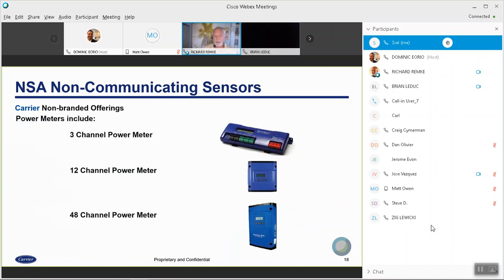And we also have these BACnet power meters for sub-metering. We have a 3-channel model, a 12-channel model, and a 48-channel model. And all of those are in our catalog. And there's a whole series of CTs and VTs that go along with that, to round out your setup and hook these up. Some of these are utility grade meters so that you can get very accurate readings, something that you can bill by.